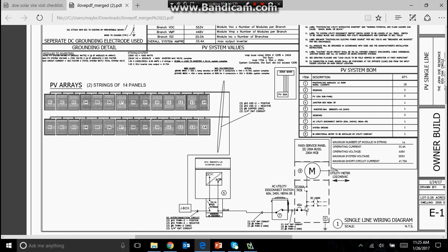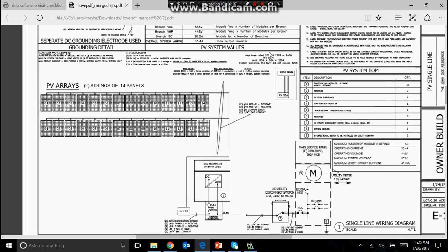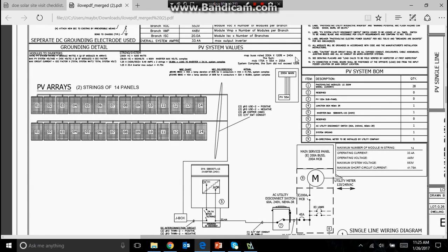So first we calculate 120% of that 200 amp rating, which is 240 amps. We cannot go over 240 amps when we add our main circuit breaker and our photovoltaic. This is a very important rule. It prevents a lot of fires.